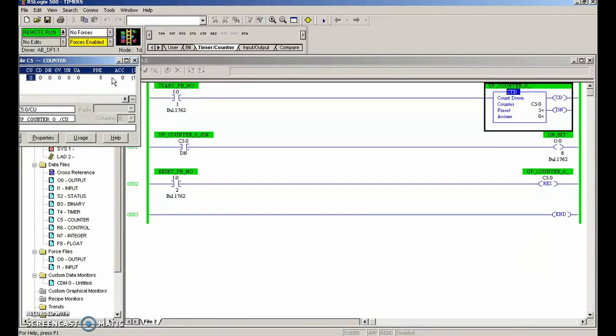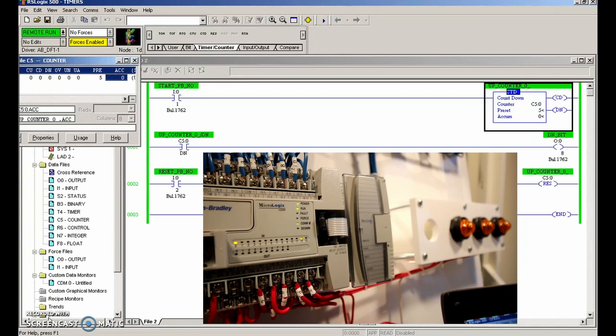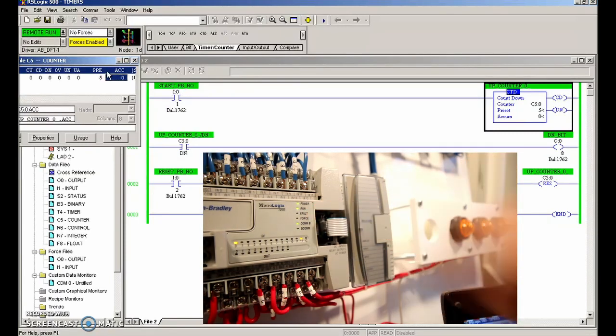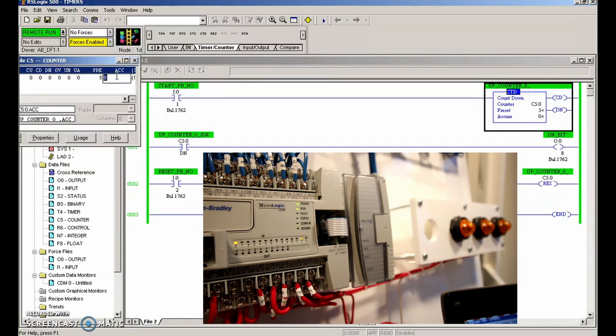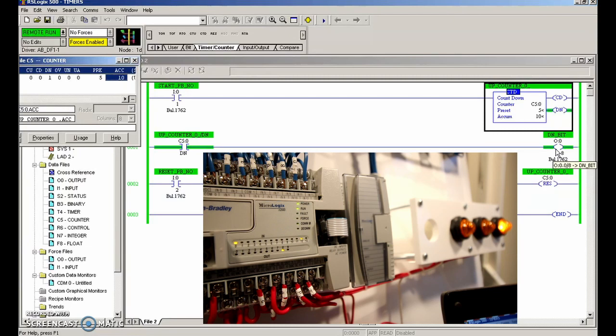Let's see if we can change the accumulated value on the fly. What I did was change the value for the accumulated while in run mode - you can see power and run LEDs illuminated. I'm going to make it greater than five. If the preset and the accumulator are equal or above, then the done bit will set. I'm going to change this to 10 - as soon as I hit enter, that light should turn on. We can see the done bit has set and output number 8 is on.